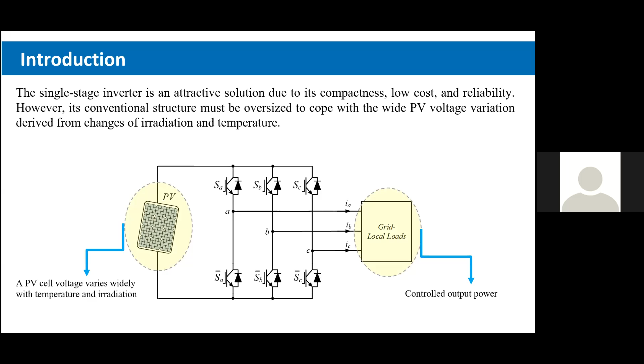To overcome this issue, some topologies have been proposed. As a first solution, maybe the simplest way, a transformer can be used between the voltage source inverter and grid to cope with the range of the PV voltage. The main advantage of this topology is that it is easy to implement and no extra control circuits are needed.